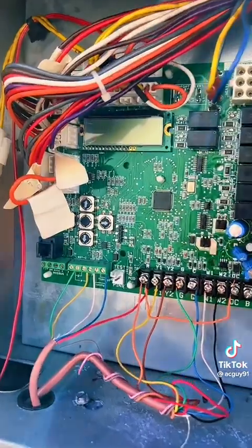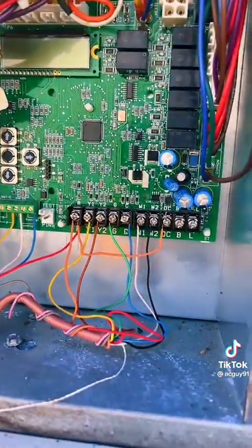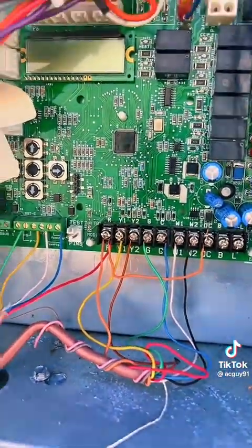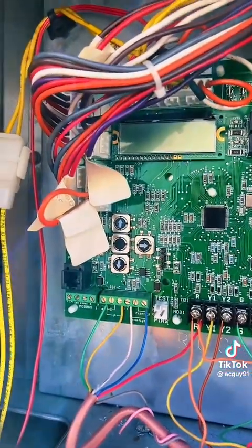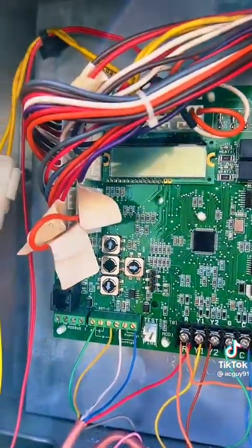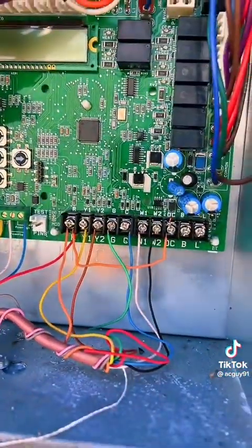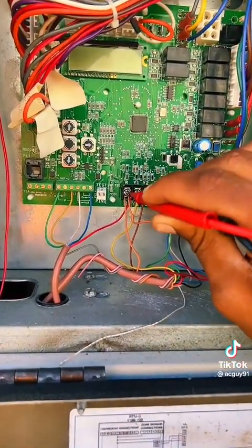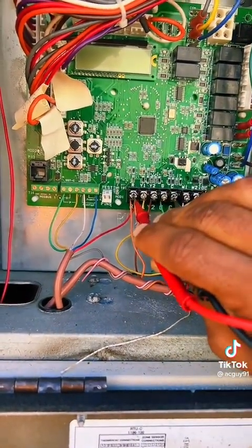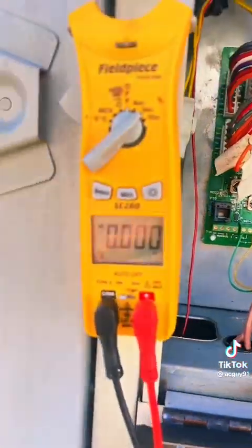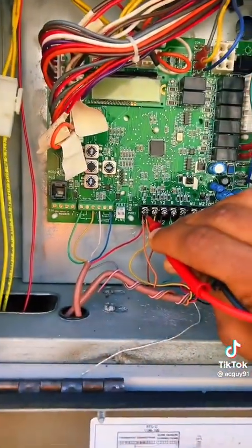There's my control board. I've got no display. Now I'm gonna check if I have 24 volts coming into the board, because just because I have no display doesn't necessarily mean I don't have power. It just means I could have a bad display. So let's verify that. Obviously that would have been way too easy. So I'm checking across red and common. That's my power in, and I've got nothing. So let's keep going, guys.